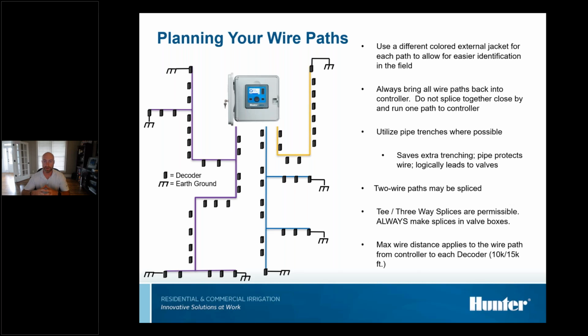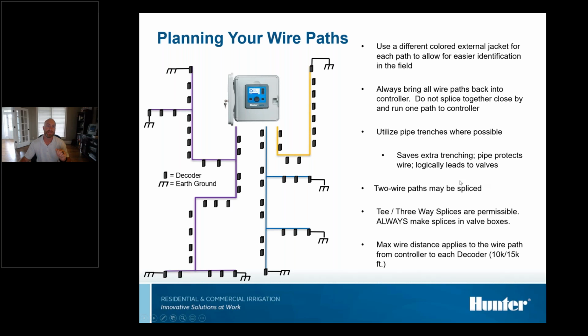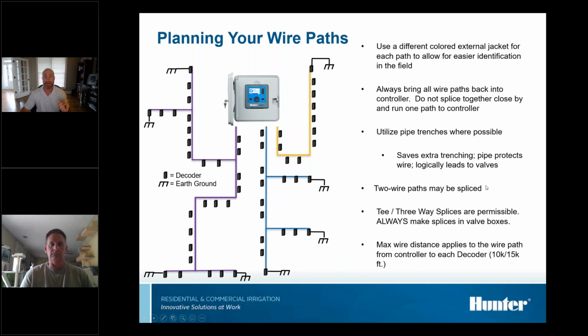You can splice a 2-wire path anywhere. 3-way splices like we've got here in the purple and then here in the blue, those are permissible. But a big disclaimer when it comes to splicing is always, always, always put any splice in a valve box where it is accessible. Dirk can probably back me up on this, but probably 90% of all issues that we see with 2-wire systems happen at a splice. It's a bad splice. Is that a fair assessment, Dirk?